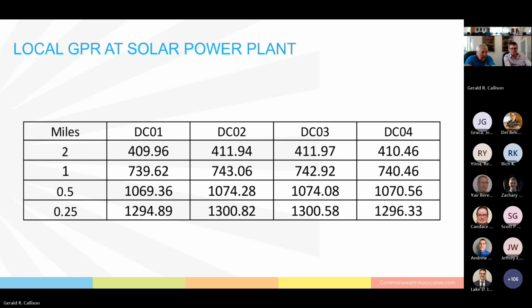Okay, so the ground potential rise that we're looking at is for a fault that actually occurs on the high side of the utility transformer. That is the fault that creates the maximum ground potential rise at both the collector station and the solar plant. So as you can see, the voltage at the solar plant, when you're 2 miles apart, is approximately 410 volts. At 1 mile, that voltage increases to around 740 volts. At a half mile, it's closer to 1,070 volts. And a quarter mile apart, it's almost 1,300 volts.